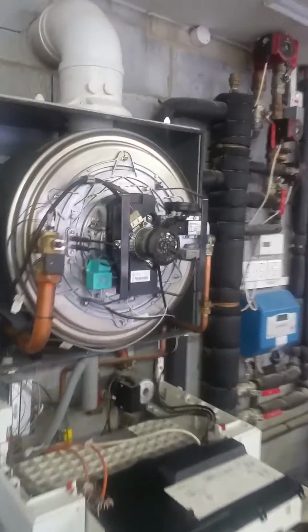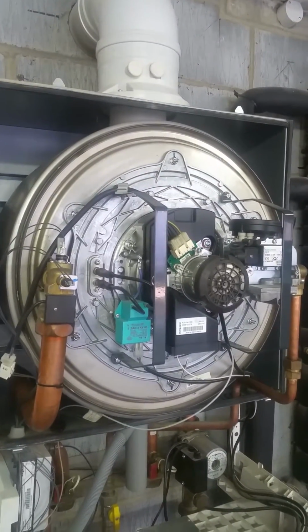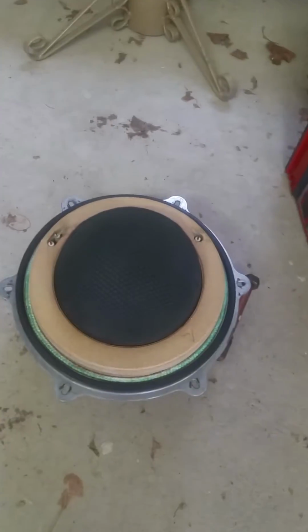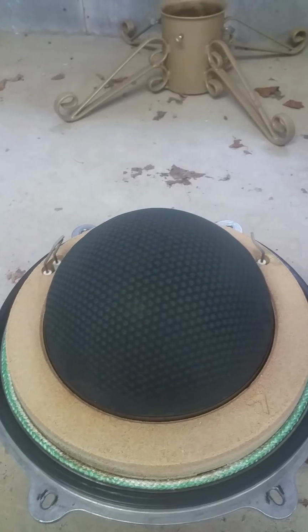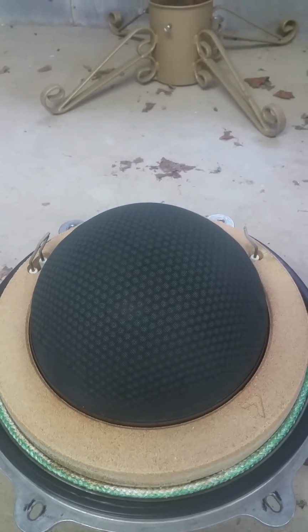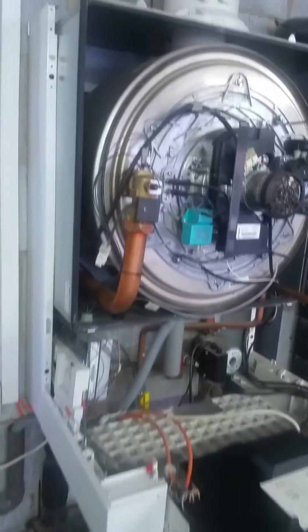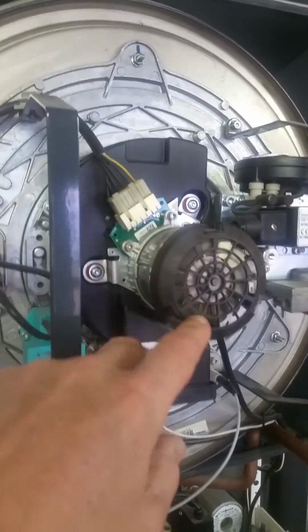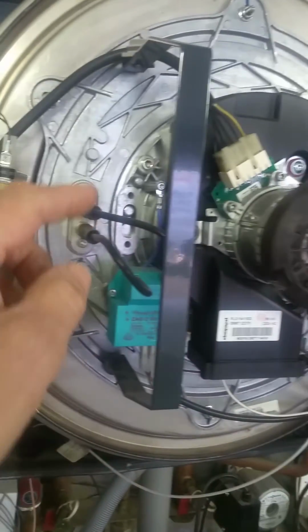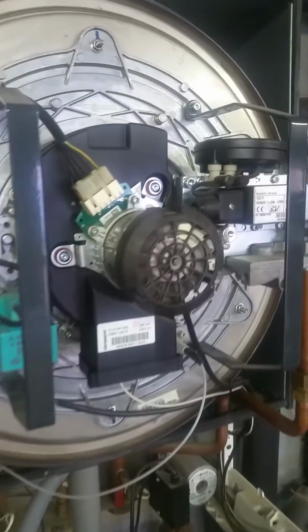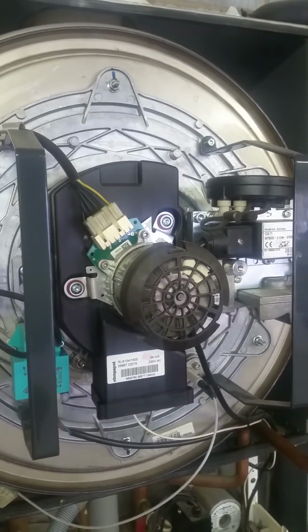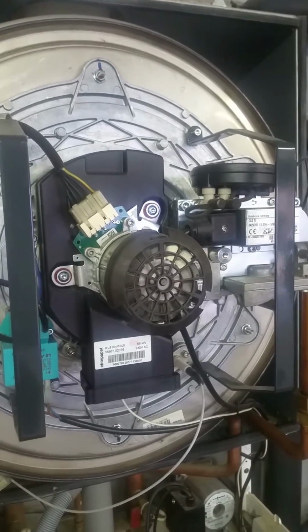The fan mounts with a few nuts on those studs that I was telling you about, and mounts on the front. And we've got this very beautiful burner arrangement. This is a low NOx, all singing, all dancing burner from Viessmann. I don't know that much about it, to be fair. The weakness on these boilers, on the 300, was the fan and the gas valves, and I did quite a lot of those exchanges. Fans, there's a little plastic piece just inside here that shears off and leaves the fan rattling around and unable to drive air, and I would imagine that was modified once the fans had been changed from the early models, as there didn't seem to be any recurrence.